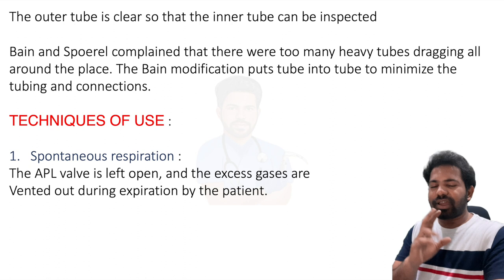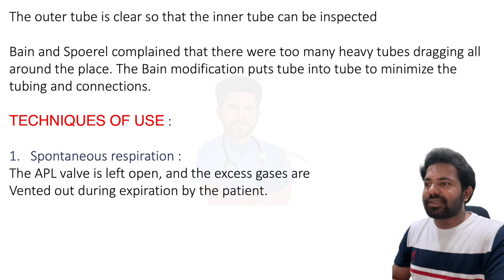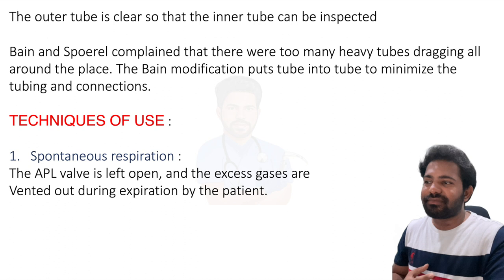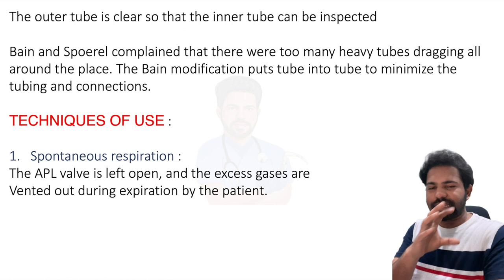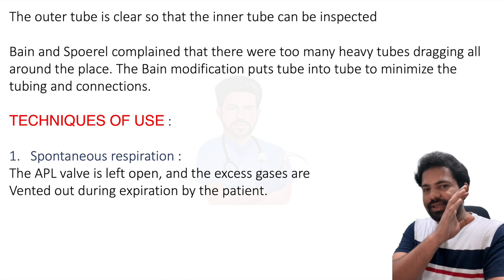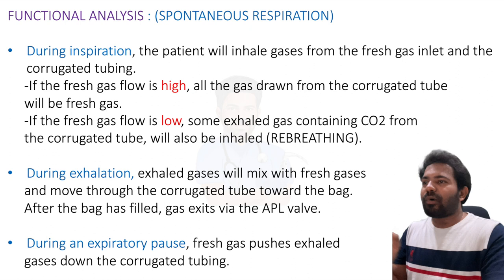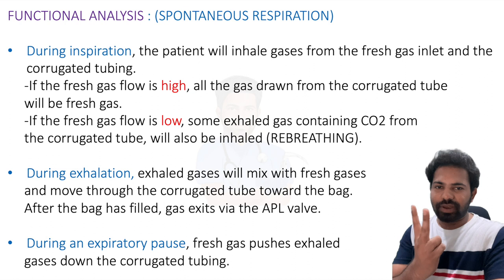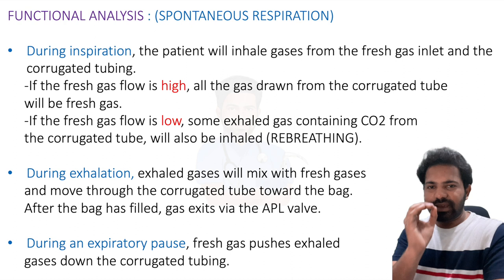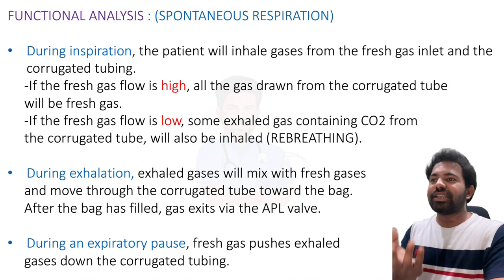The Bain circuit can be used for spontaneous respiration as well as controlled ventilation. During spontaneous ventilation, when the patient breathes by himself, the APL valve is left open and excess gases are vented out during expiration. You are not squeezing the bag; the expired gases exit through the APL valve outlet. The functional analysis covers three phases: inspiration, expiration, and expiratory pause. During inspiration, the patient inhales gases from the fresh gas inlet and the corrugated tubing.